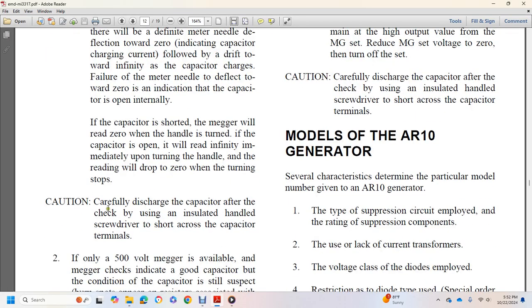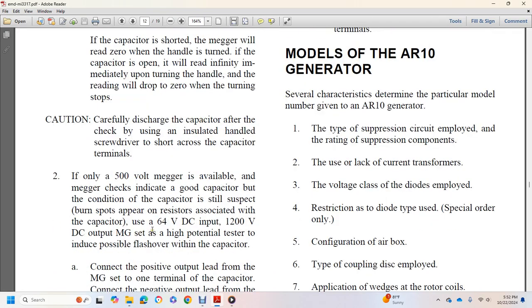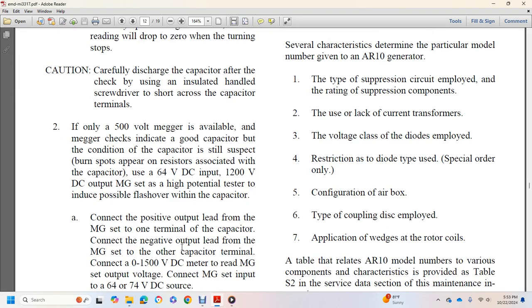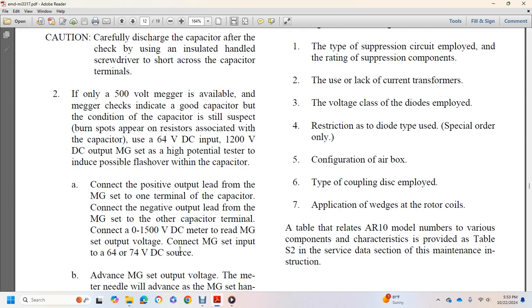Carefully discharge the capacitor after checking, using an insulated handle screwdriver to short across the capacitor terminals. If only a 500 volt megger is available, the megger may indicate a good capacitor, but the condition of the capacitor is still suspect. If burn spots appear on the resistors associated with the capacitor, use a 64 volt DC input, 1200 volt DC output MG set with a high potential tester to induce a possible flashover across the capacitor. Connect the positive output lead of the MG set to one terminal of the capacitor and the negative output lead of the MG set to the other capacitor terminal.